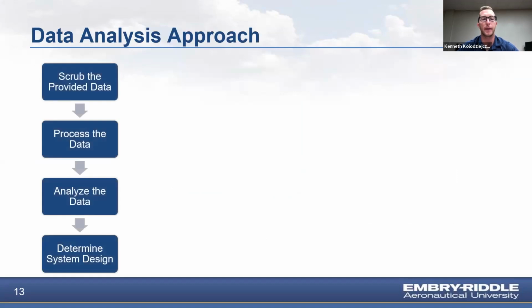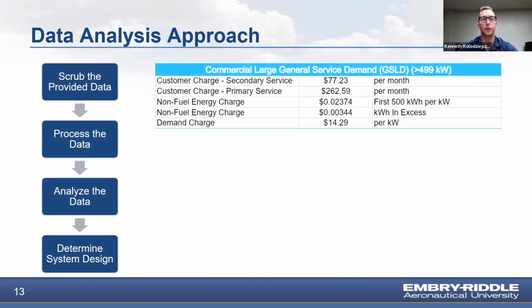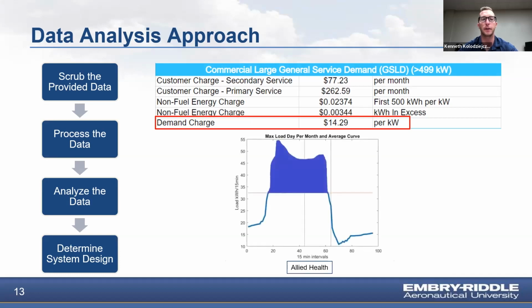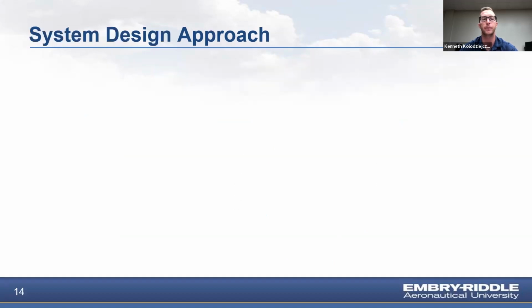Data analysis began with sifting through the provided information. The utility rates file revealed that the $14.29 per kilowatt demand charge was a large proponent of FAMU's utility bill. The 15-minute energy profile data was exported into a MATLAB code that made a graph for each building with the max daily peak of each month and their average. It was clear that to make the most financial impact, the system should be designed to peak shave the highest energy demands of each building.